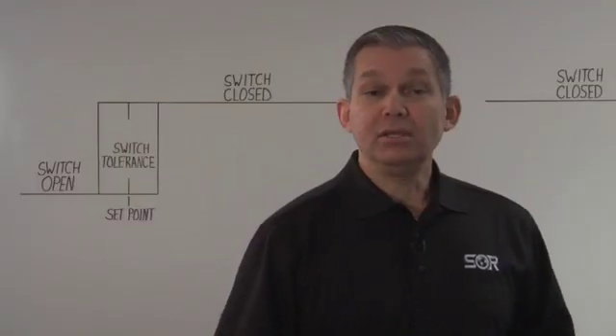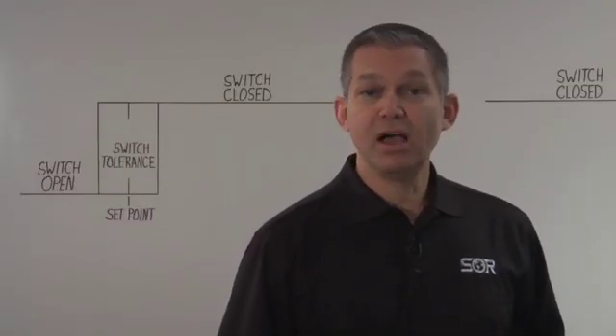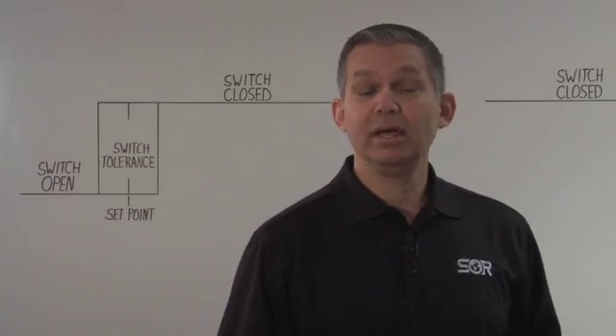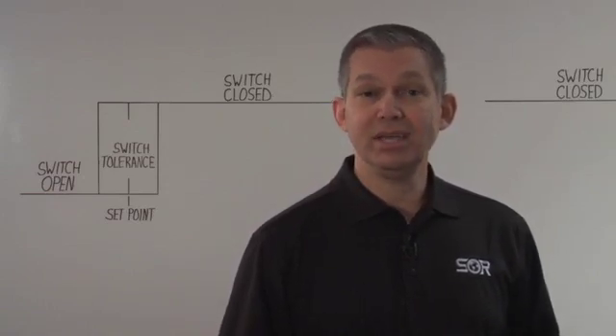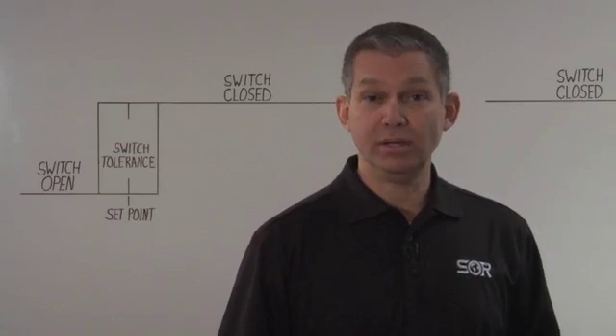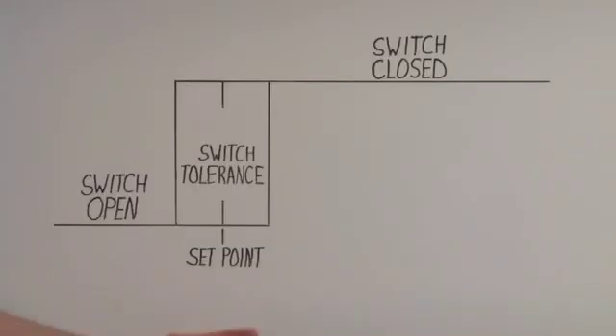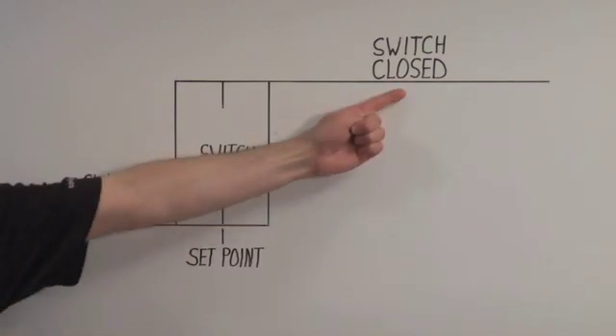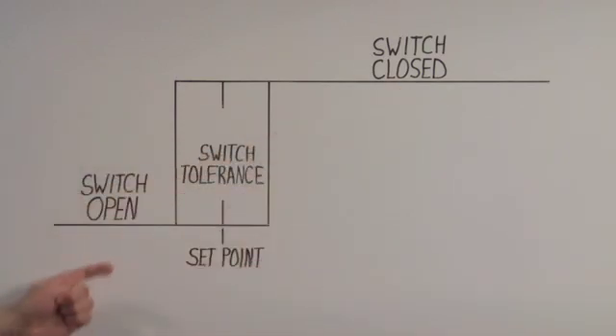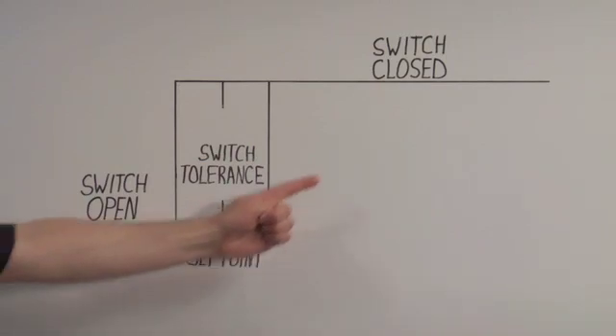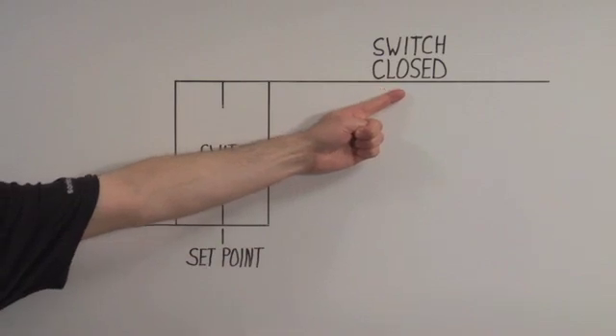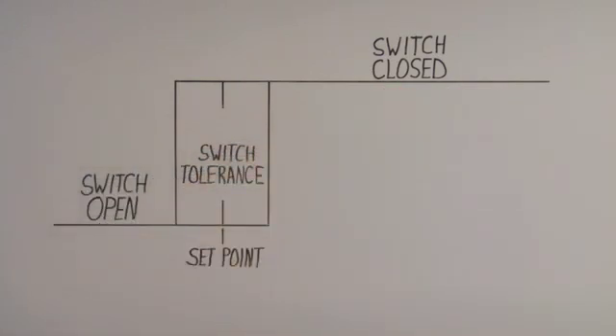We have looked at the window or default configuration for the 805QS switch output. As I mentioned earlier, the 805QS can be configured three different ways. So let's take a look at the other two configurations. Here is the second diagram. It shows the single point opened closed switch point type. If the switch is off, open, it will close when the pressure of the media reaches the set point and will remain on closed as long as the pressure is greater than the set point.